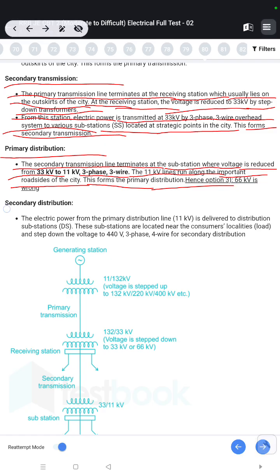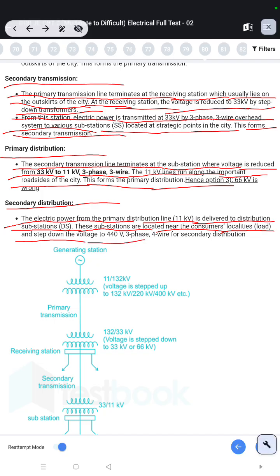Secondary distribution: the electric power from the primary distribution line at 11 kilovolt is delivered to distribution substation DS. These substations are located near the consumers' localities and step down the voltage to 440 volt, three phase four wire, for secondary distribution.